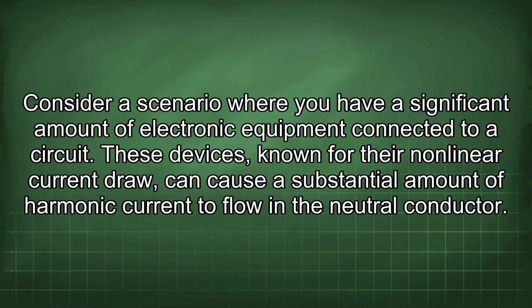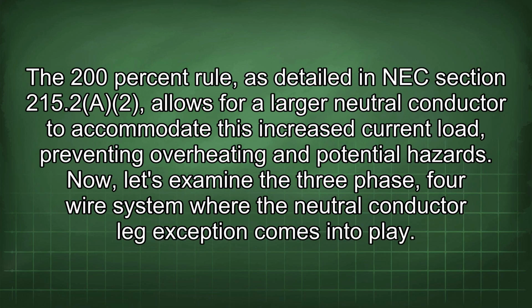Consider a scenario where you have a significant amount of electronic equipment connected to a circuit. These devices, known for their nonlinear current draw, can cause a substantial amount of harmonic current to flow in the neutral conductor. The 200% rule, as detailed in NEC section 215.2(A)(2), allows for a larger neutral conductor to accommodate this increased current load, preventing overheating and potential hazards.